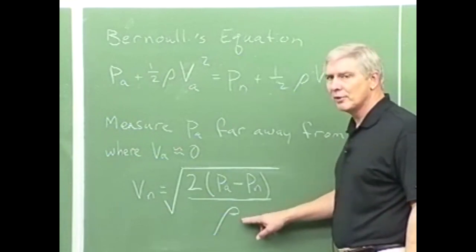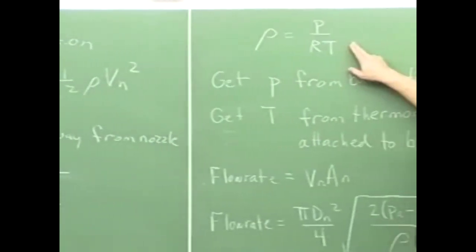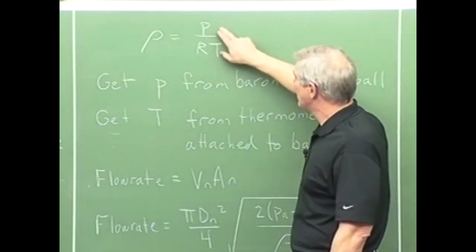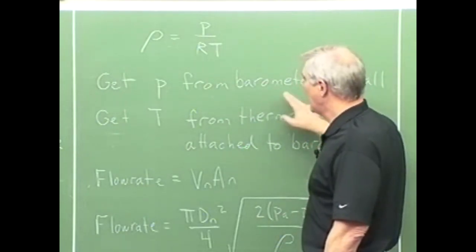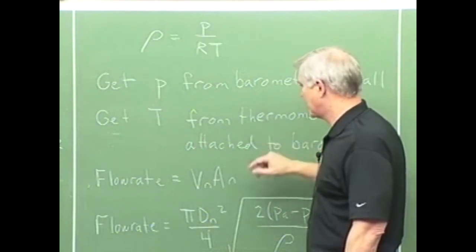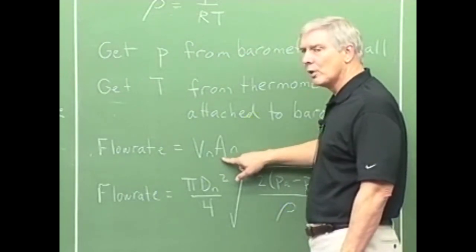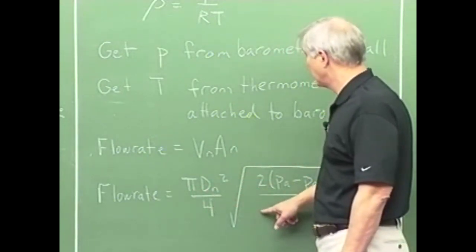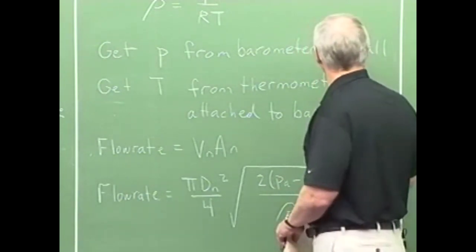In order to get the, now what we don't have at this point is the density of the air. To get the density of the air, we use the equation of state, where density is equal to P over RT. To get the pressure in the room, we have to use the barometer, which is on the wall, right next to the fan performance apparatus. And then there's also a thermometer attached to that barometer, and so we get that from the thermometer. The flow rate is just equal to the velocity at the nozzle times the area of the nozzle. Well, we're given the diameter of the nozzle, so that would be pi D nozzle squared over four times the square root of two delta P over rho, the velocity.